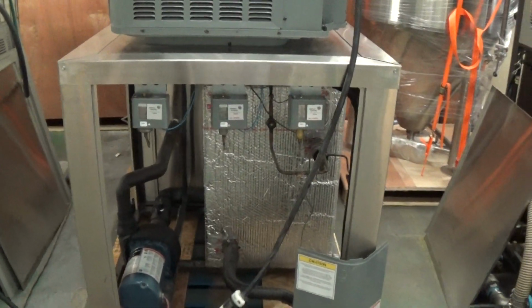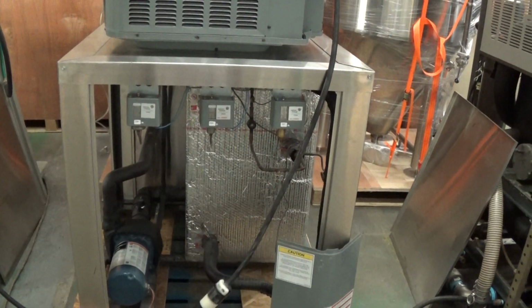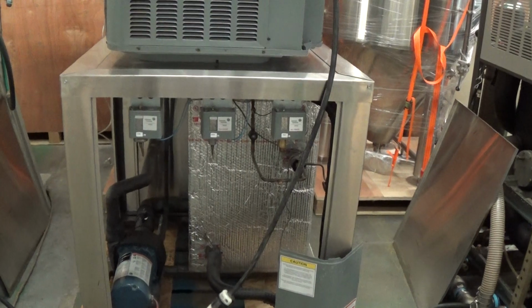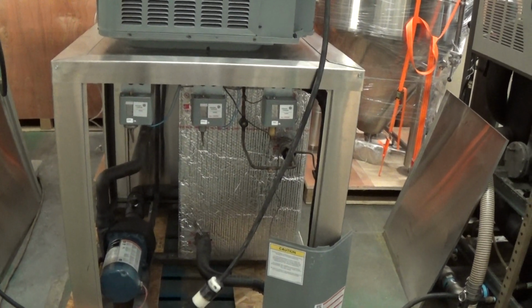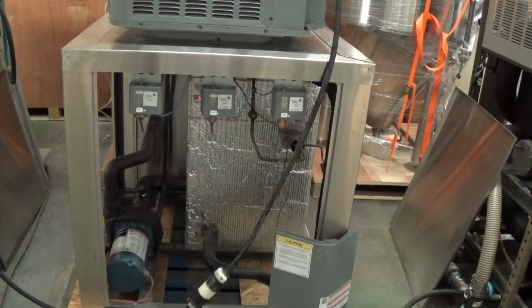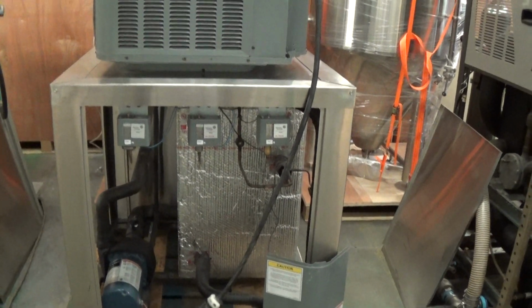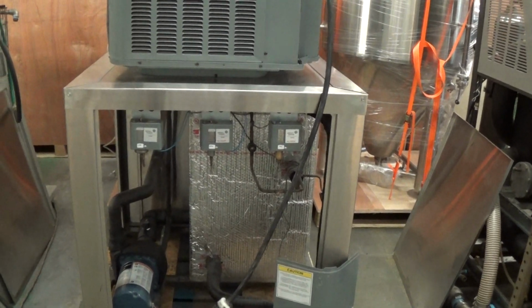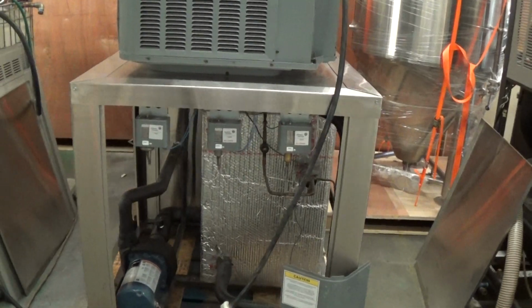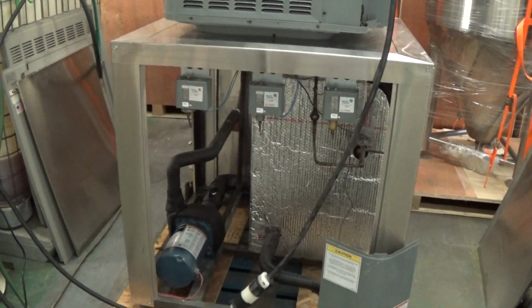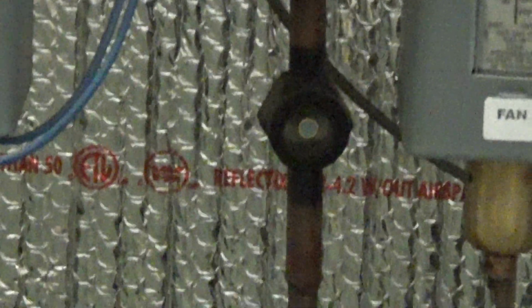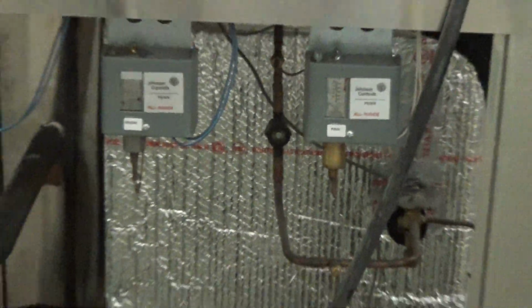It has an adjustable high pressure switch and an adjustable low pressure switch. It also has fan cycling, based on pressure. So when the compressor is running, the fan does not necessarily always have to be running. It depends on ambient air conditions. And the unit does come with a refrigerant sight glass also.